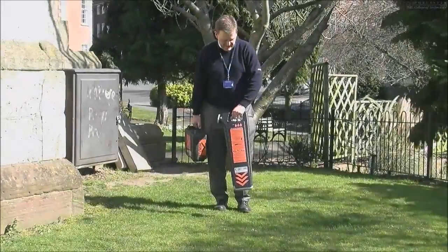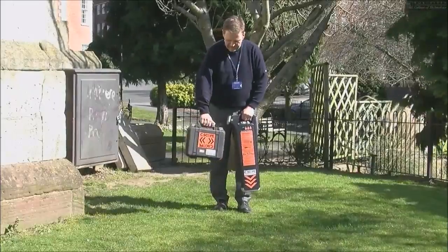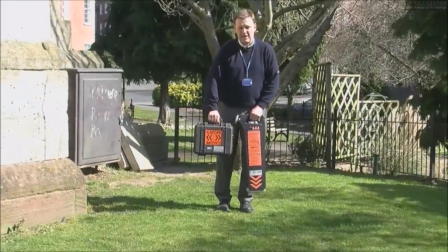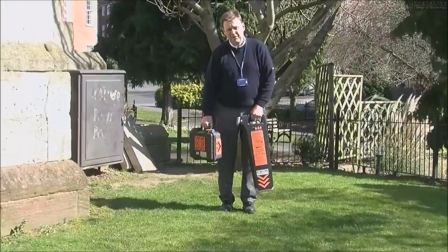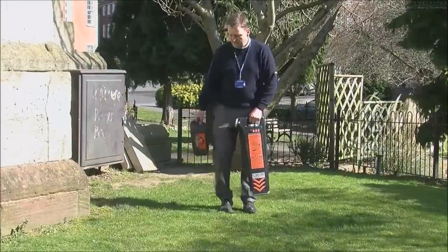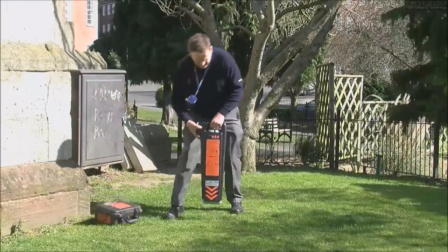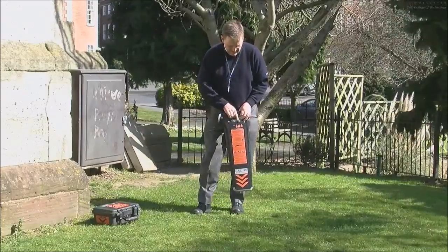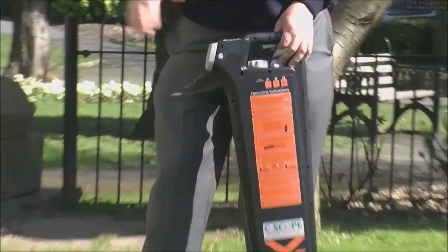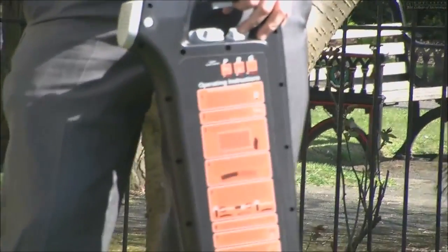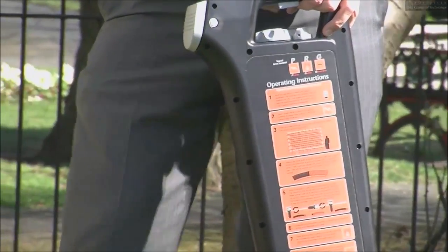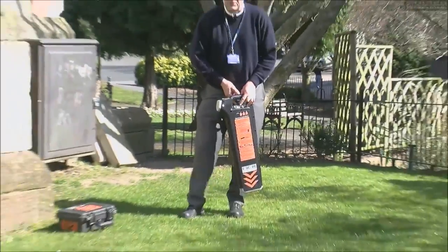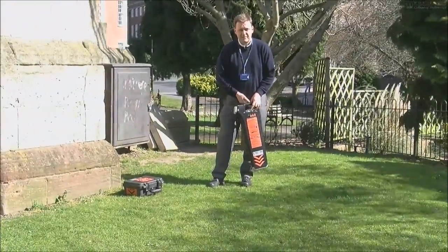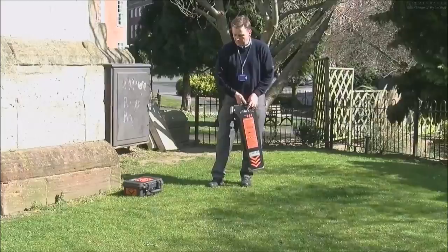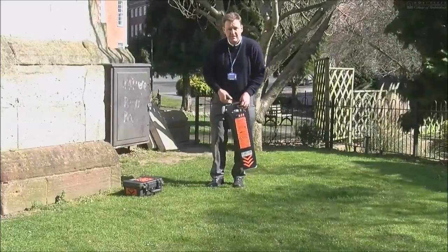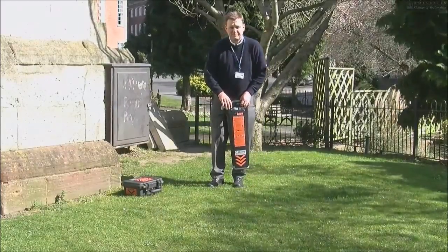Okay, this is the cable avoidance tool, the CAT, and this is the Genny. What we're going to do now is we're going to find a cable that is buried underground. Now, under normal conditions, we would use the power setting and literally trace the ground along until we actually found the cable. But as the light isn't on, we are going to have issues of actually trying to find the cable itself.